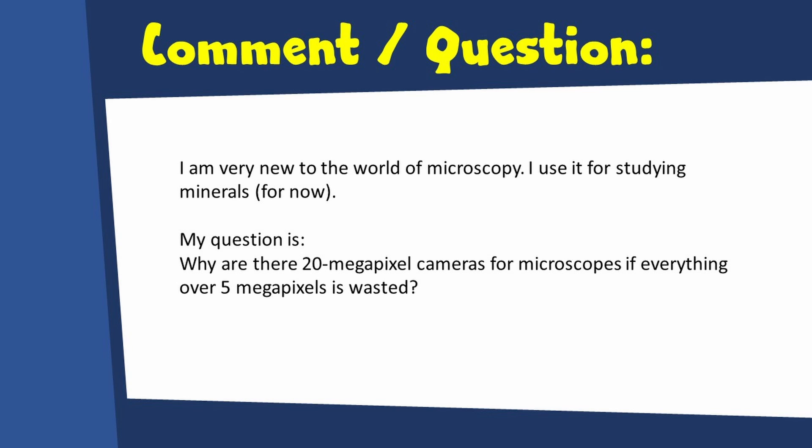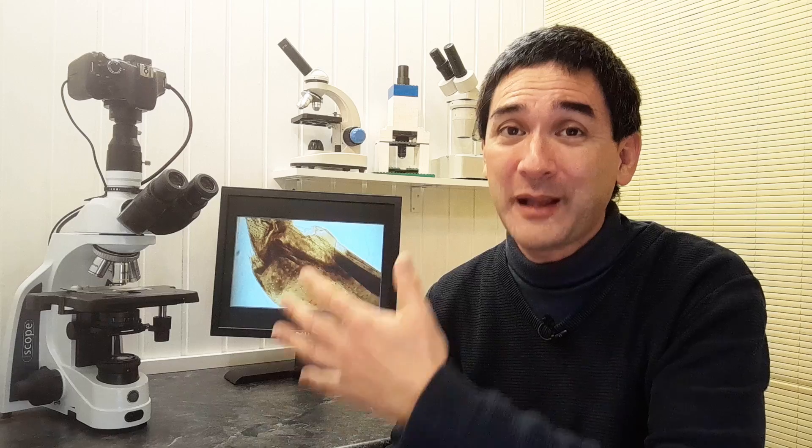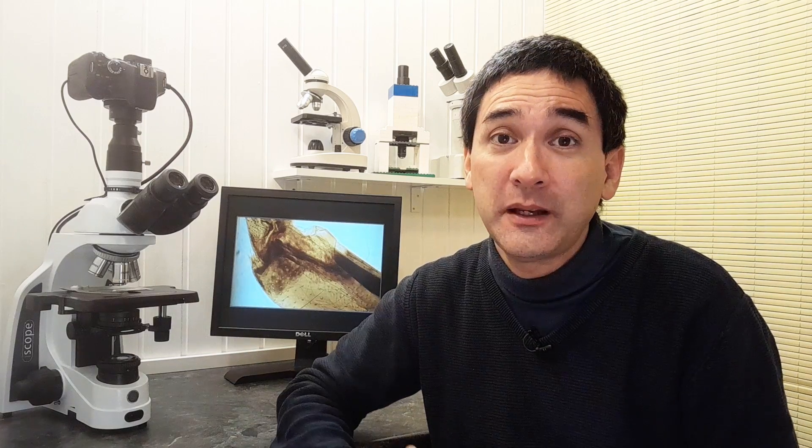Well, first of all, thank you very much for the question. Some time ago, I did make a video explaining that the microscope cameras that have more than approximately 5 megapixels are probably a waste of money because the microscope is not able to produce the image quality that the camera is able to capture. So in other words, if the image quality is low, then it's the microscope and not the camera that's to blame because the microscope resolution is limited.